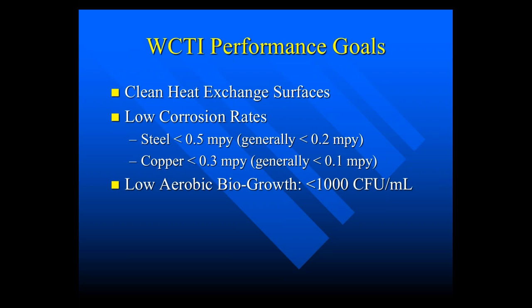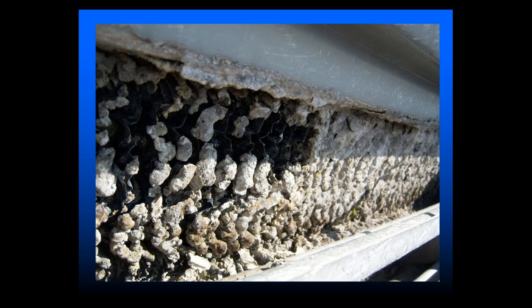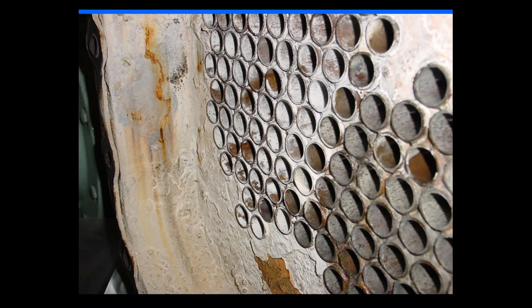Why soft water makeup? Soft water eliminates the hardness scale, which reduces efficiency. Scale can build up on tubes by fractions of inches or even inches, and that will decrease your efficiency and decrease heat transfer. If you've got makeup water coming in with high hardness and alkalinity, you will have deposits. This is one of the most severe cases I've seen — this is the fill for the tower that the water goes through, and obviously not much water flow is happening there. And here is the scale that's on the tubes; scale is a great insulator, so again you have poor heat transfer.